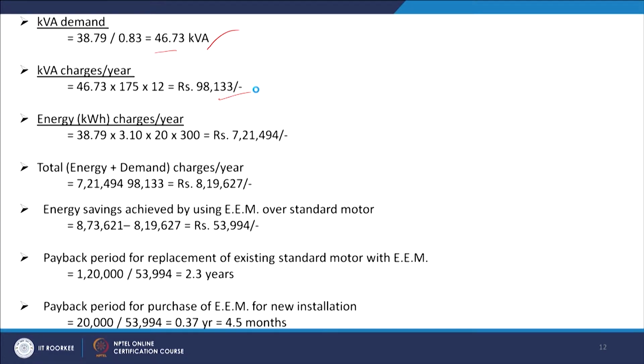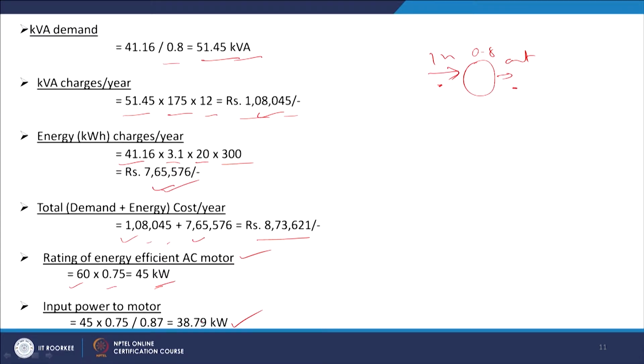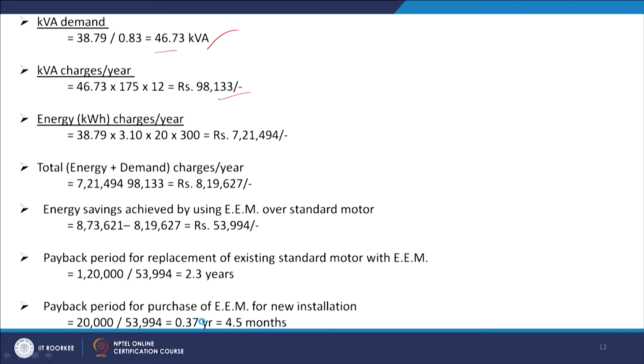And what will be the energy charge in this case? We need energy equal to 38.79 kilowatt. So, 38.79 kilowatt into 3.10 into 20 hours per day into 300 days per year. So, it is coming to 7,21,494 rupees per year. So, the total charge will be this plus this. So, we are getting energy plus demand charge, that is coming to 8,19,627 rupees.